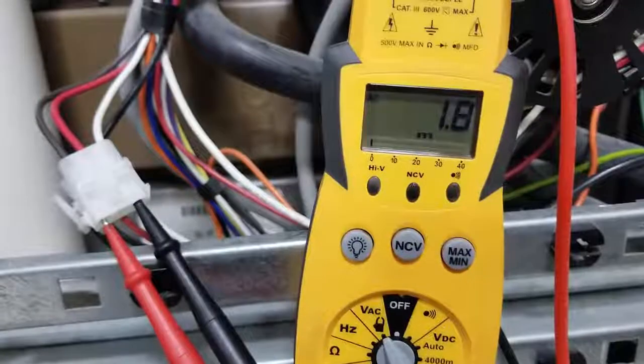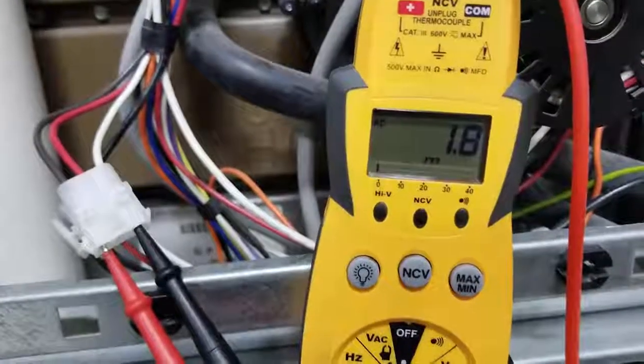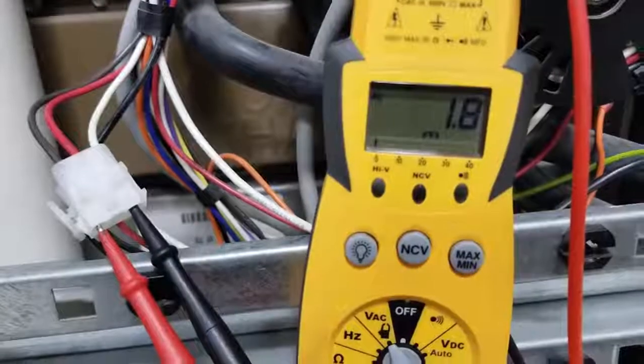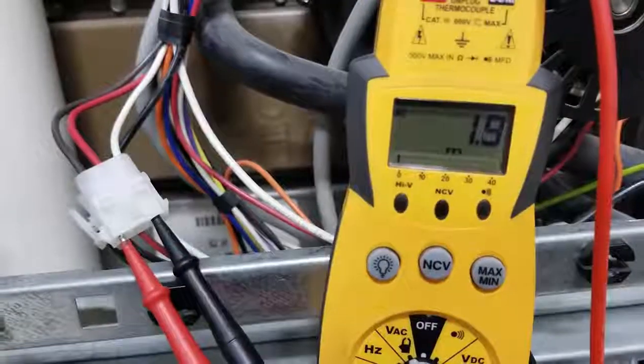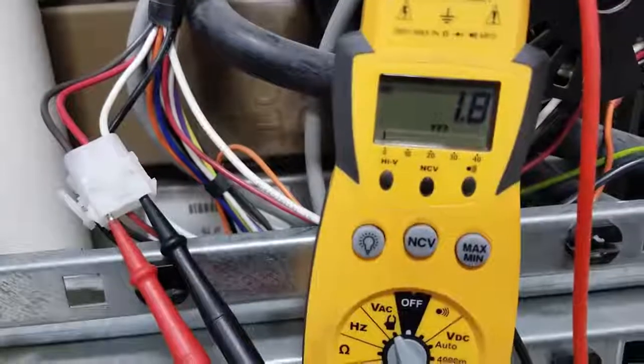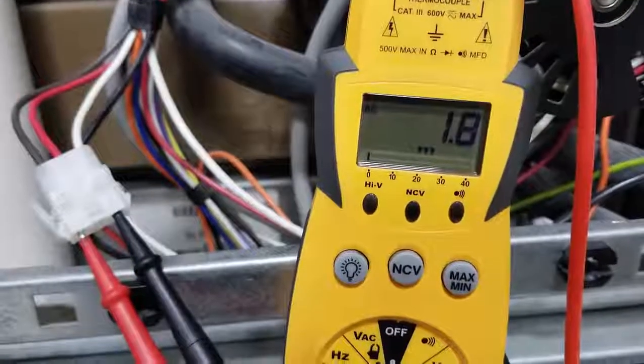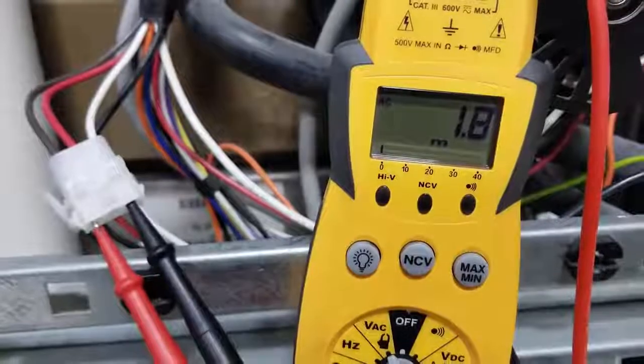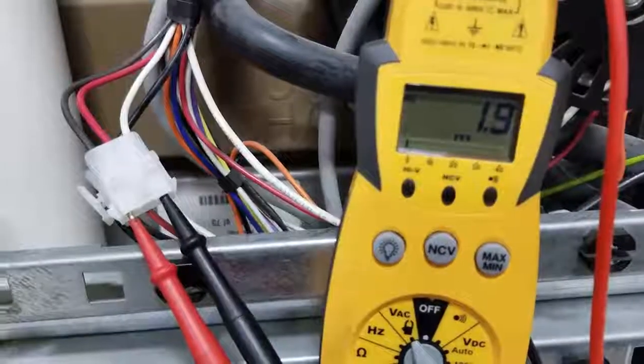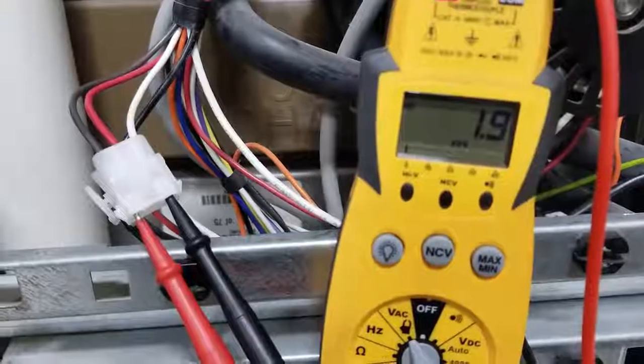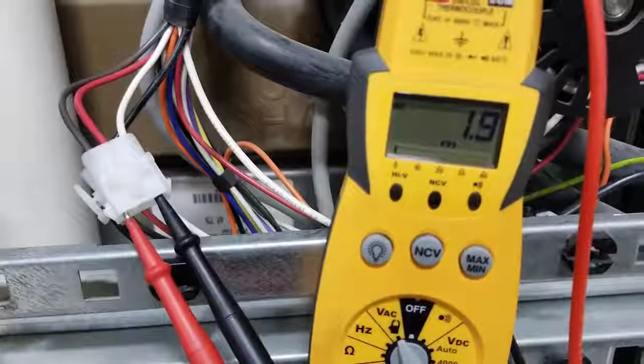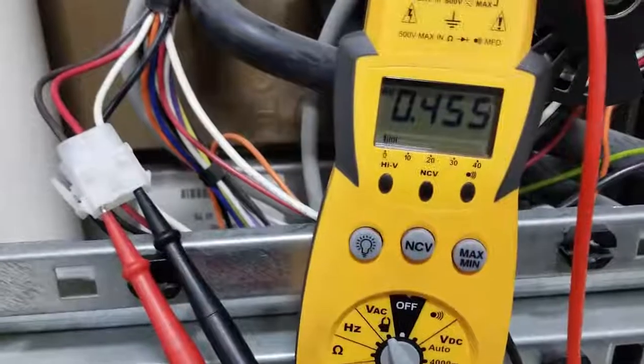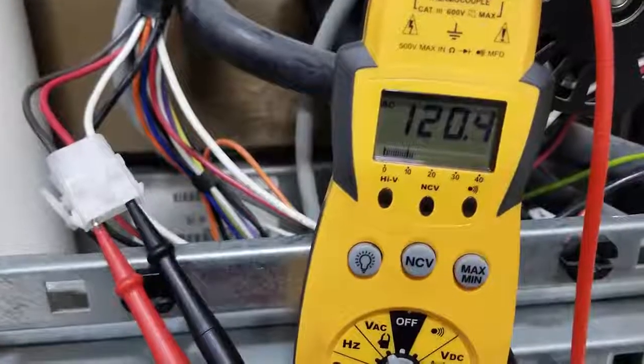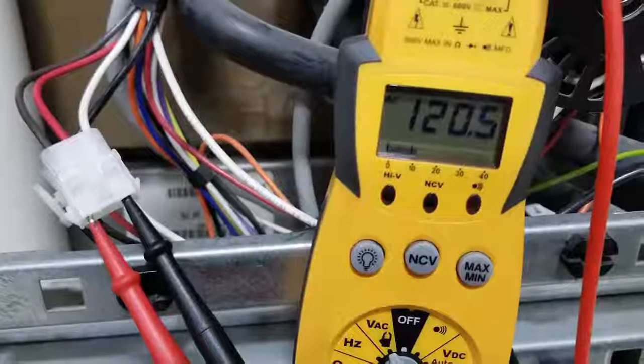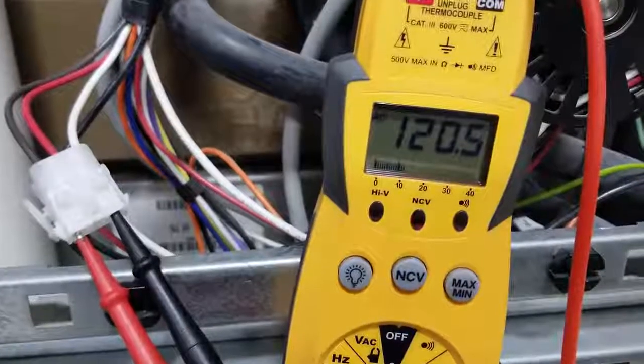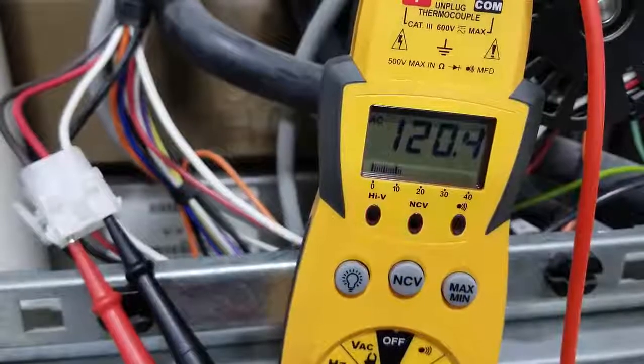Okay, I've disconnected or unhooked the Molex plug that goes from the circuit board to the inducer motor. I've hooked my meter leads into the Molex plug to the wires that go back to the circuit board. Currently the power is off, so I'm showing no voltage, or 1.9 millivolts, which is basically no voltage. I'm going to flip the power onto the unit, and if everything's working right, we should see 120 volts to the inducer motor. And there we go. So now we know we've got power to the inducer motor. So if the inducer motor was not operating, then we know there's a problem in the motor.